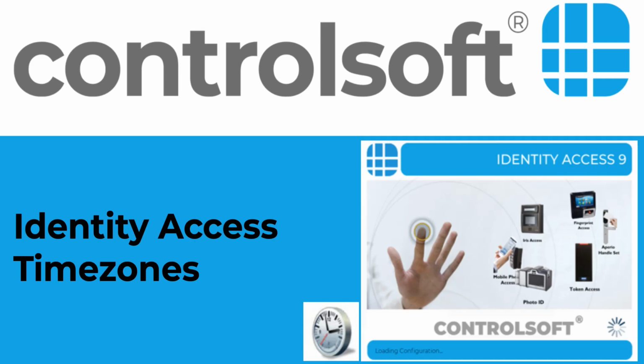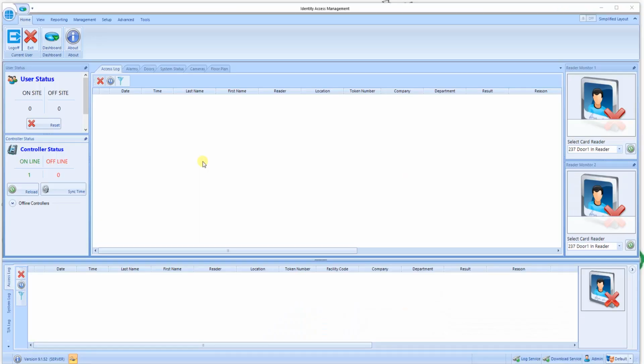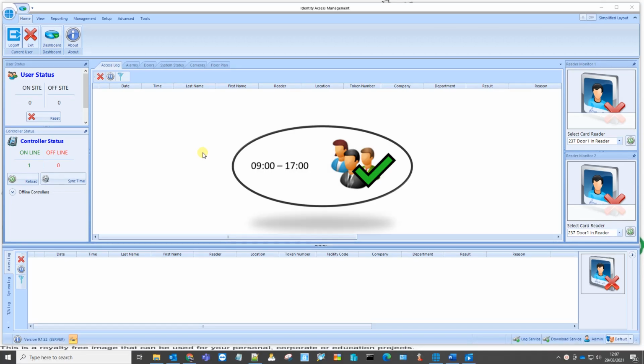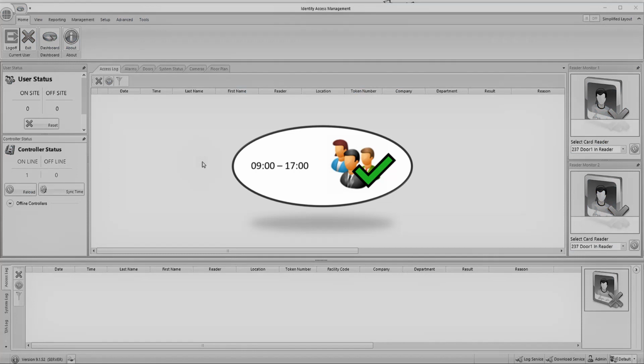In this video, we will show you how to create a time zone and how to apply it to a group in your access control system. This will restrict the access to the users within the group to specified times. For this demonstration, we will show you how to create a user access time zone for our main entrance door. This will restrict access to between Monday and Friday from 9 AM to 5 PM. After 5 PM and before 9 AM, the users will be denied access.